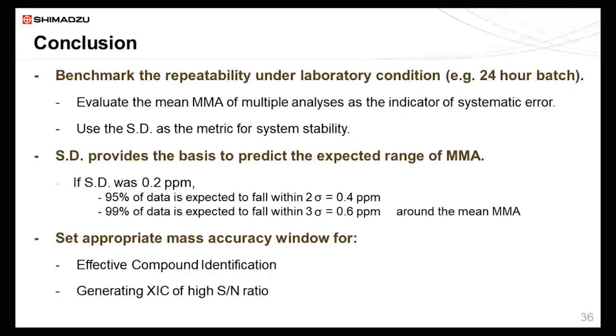So the conclusion of today's presentation is that we've got to benchmark the repeatability under laboratory conditions, for example, by doing a 24-hour batch. And these are for two purposes. We've got to evaluate the mean measured mass accuracy of these multiple analyses as an indicator of the systematic error, whether your instrument is under the influence of temperature fluctuation or any other sources of bias. And also we could use the standard deviation as a metric for system stability, i.e. the non-systematic error. And you could use this standard deviation as a basis to predict the expected range of mass measurement accuracy.